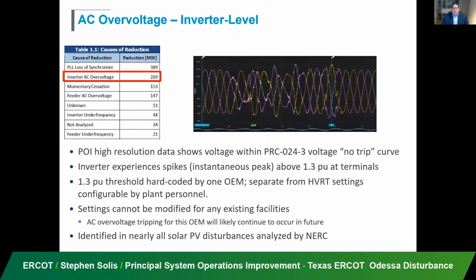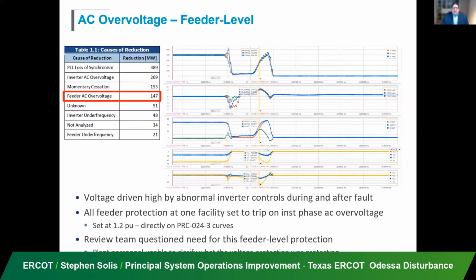When we looked at this in detail, there are a couple of things we think we can try to help by increasing some of the tolerances. But some of the equipment has hard limits. So the real takeaway here is that these solutions need to be driven by close coordination of the generating plant and include the vendor, because ultimately the vendor has to start making tolerances within their equipment that allow for a wider range without tripping off these inverters due to high voltage ride through. This is also at the feeder level where we saw it.